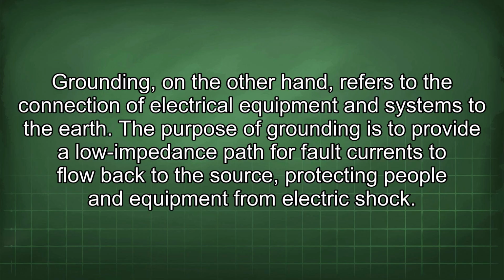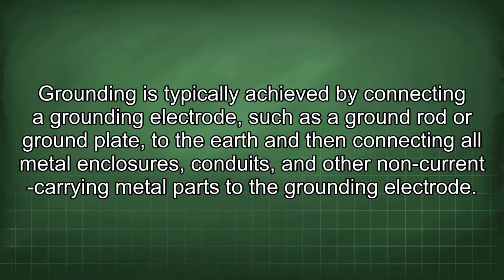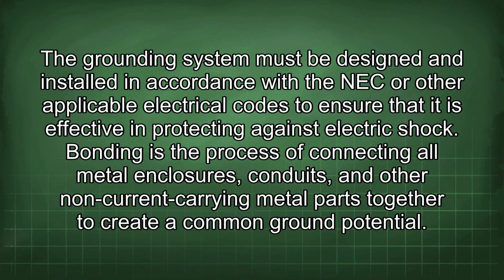Grounding, on the other hand, refers to the connection of electrical equipment and systems to the earth. The purpose of grounding is to provide a low impedance path for fault currents to flow back to the source, protecting people and equipment from electric shock. Grounding is typically achieved by connecting a grounding electrode, such as a ground rod or ground plate, to the earth and then connecting all metal enclosures, conduits, and other non-current carrying metal parts to the grounding electrode. The grounding system must be designed and installed in accordance with the NEC or other applicable electrical codes to ensure that it is effective in protecting against electric shock.